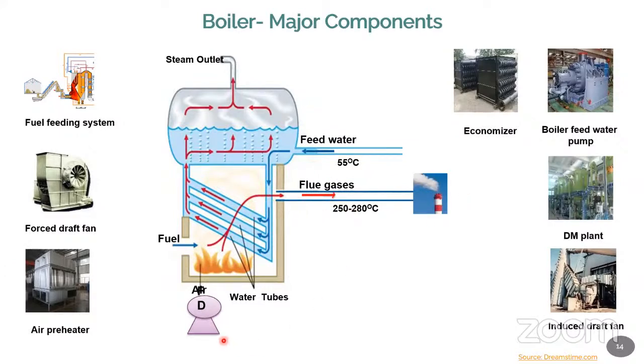Okay. Now, if you pass more air than required, then what will happen? This is very, very important. So that is why we need to operate the FD fan at the very correct speed. If you are pumping more air, more oxygen will be pumped into the system. You are thinking that the more oxygen you supply, the more quickly the burning will take place. No, it is not correct. Why? Because when you are pumping more air, automatically all the heat will be taken by the air itself and will go out in the flue gas, not to the system, not to the water. Okay, that's a very important problem. So you need to properly optimize the speed of the forced draft system.